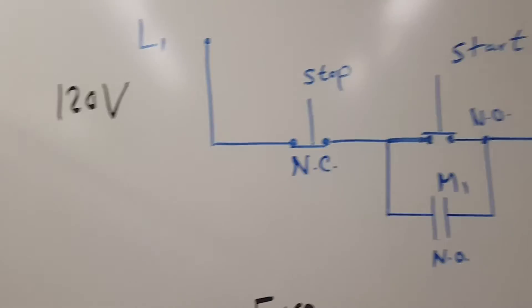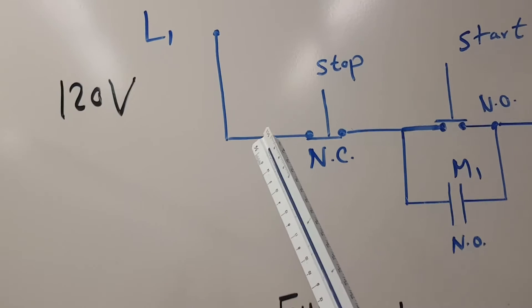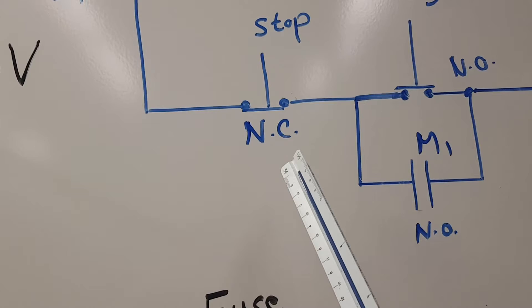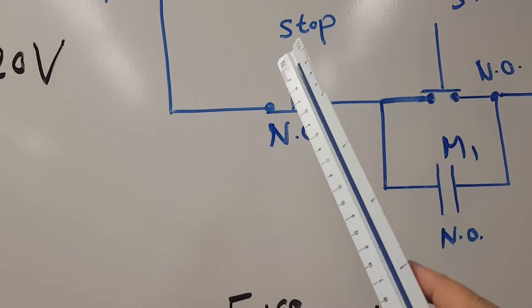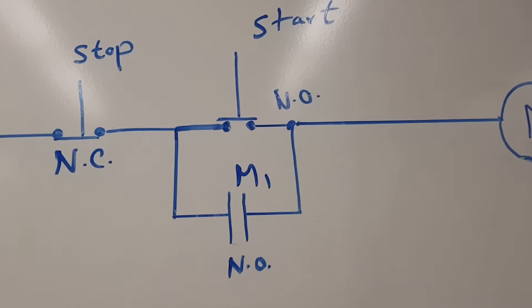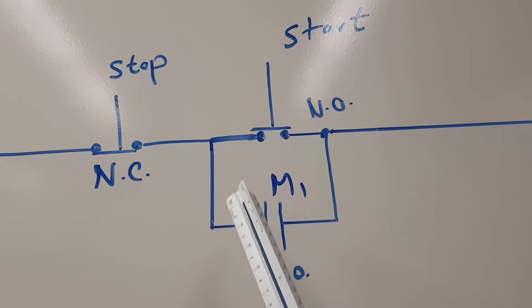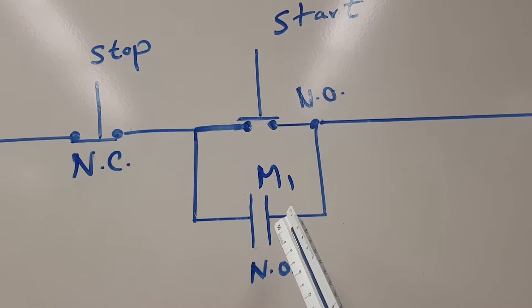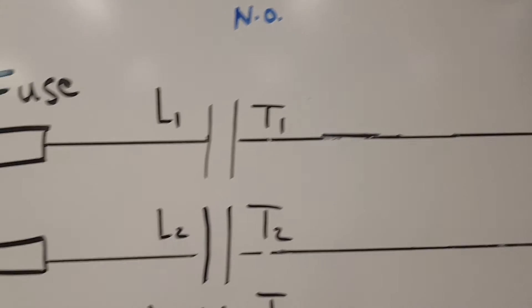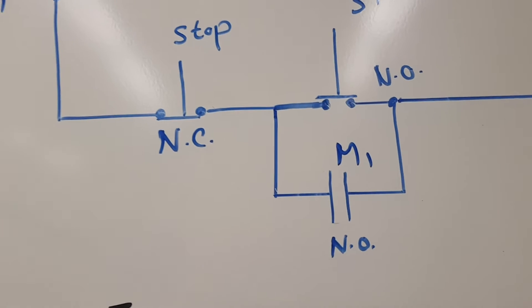Now let's go to the control circuit — the blue one. We start from the single-phase voltage at 120V. In series with that we have a normally closed switch, which is the stop button. In series with that is a normally open switch, the start button, and in parallel with it there is a contact called M1. The contactor in the power circuit is also M1, so these are controlled by the same relay.